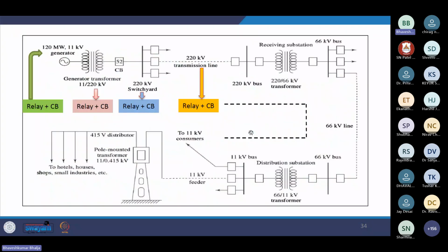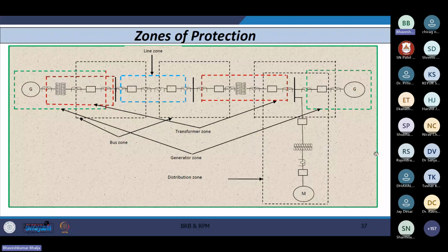Now, one more thing. You can see that our entire power system network is divided into several zones. Why zones? Why not only a single device? A single device is not used because the line is very long, and the characteristics of each equipment are different and non-linear in nature. Let's say a generator, power transformer, bus bar, then the transmission line, and again the transmission line at the receiving end. Then further distribution takes place, and so on.